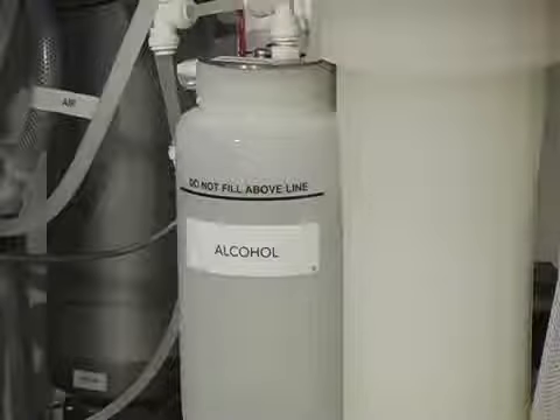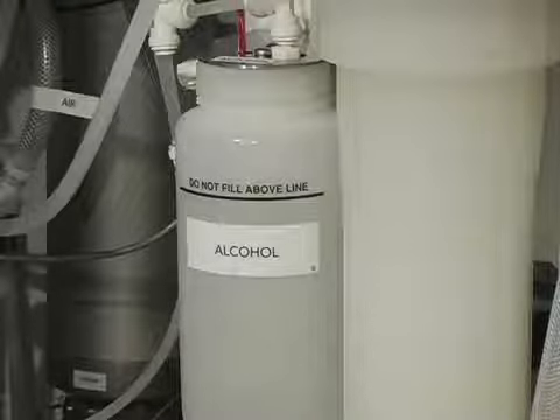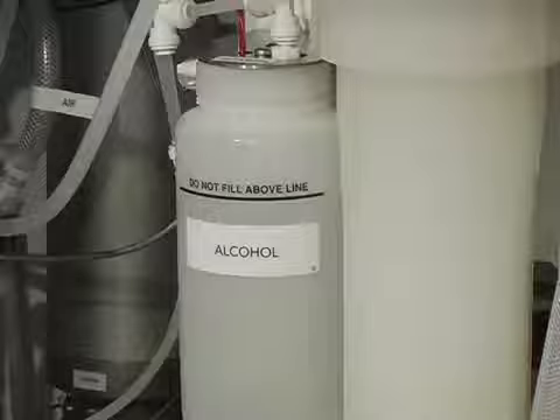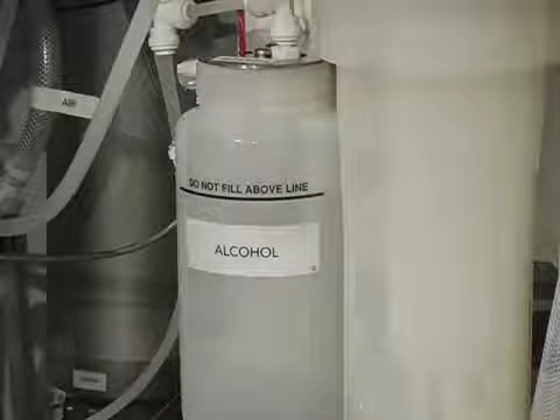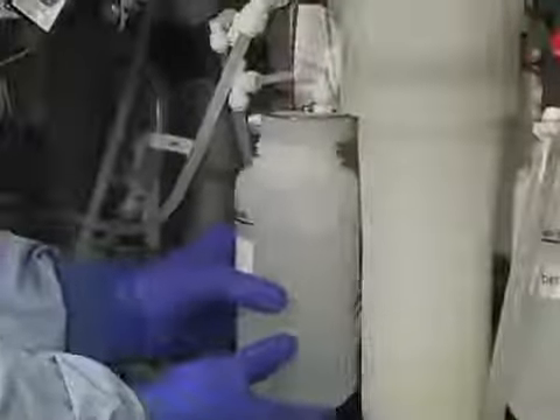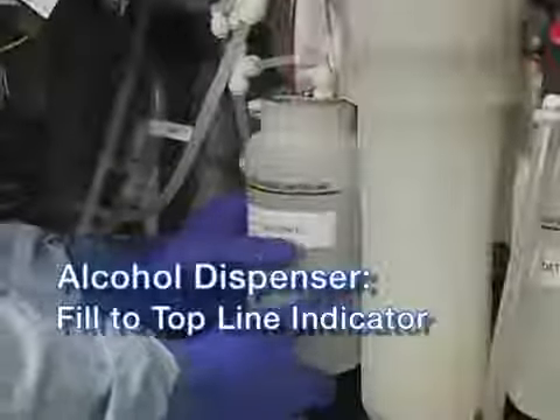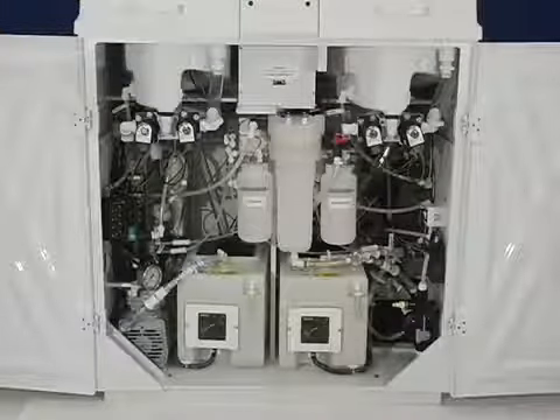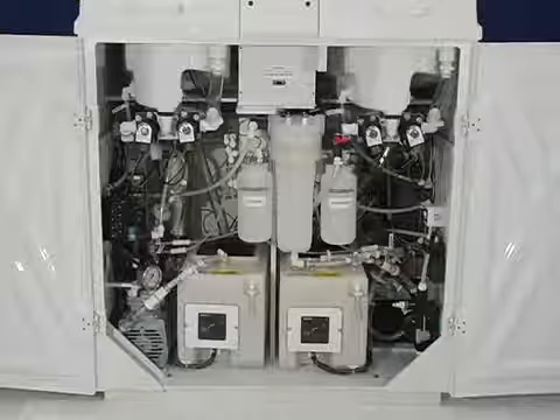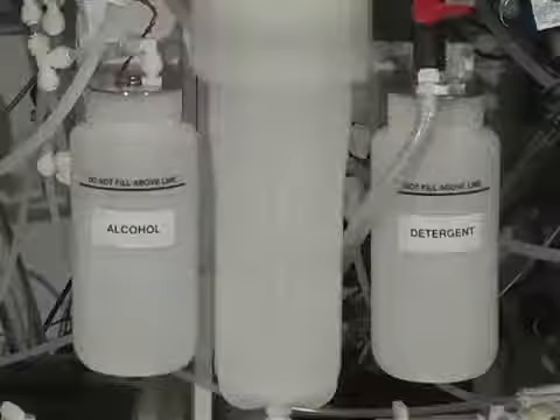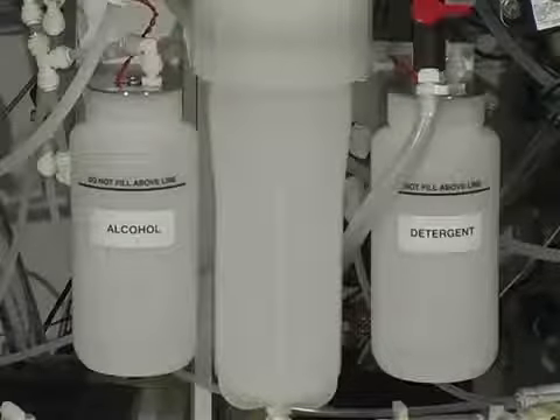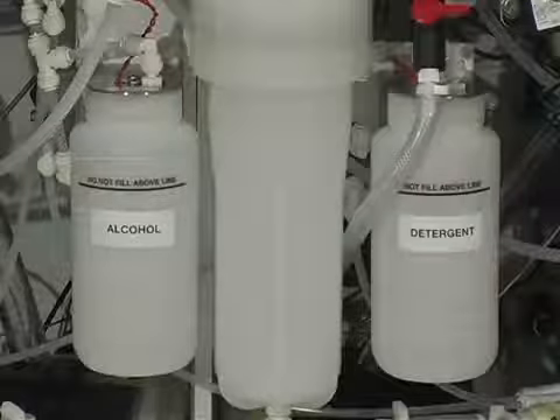An alcohol purge is required at the end of each endoscope reprocessing cycle to prevent the growth of microorganisms and biofilms. Check the supply in the reservoir. 70% isopropyl alcohol should be filled up to the 800 milliliter line indicated on the reservoir. The internal filter checks must be performed on both stations of the DSD-201. The detergent and alcohol reservoirs are common to both stations of the unit.